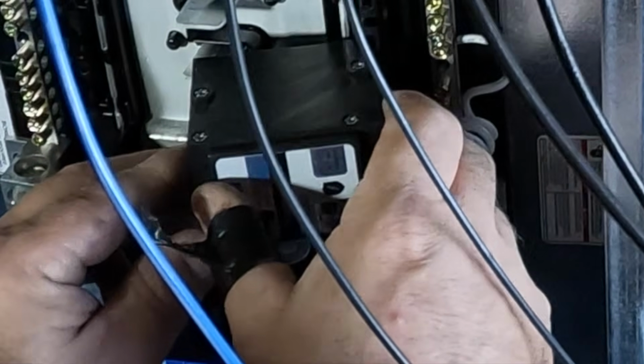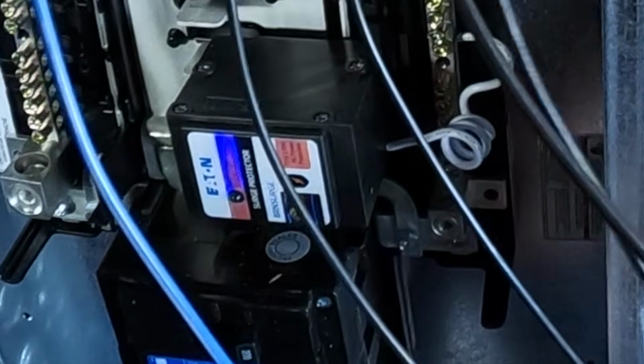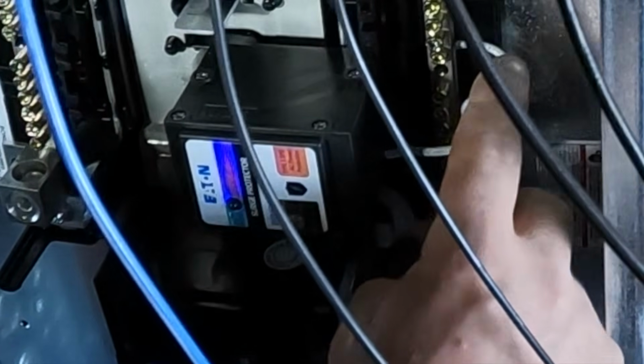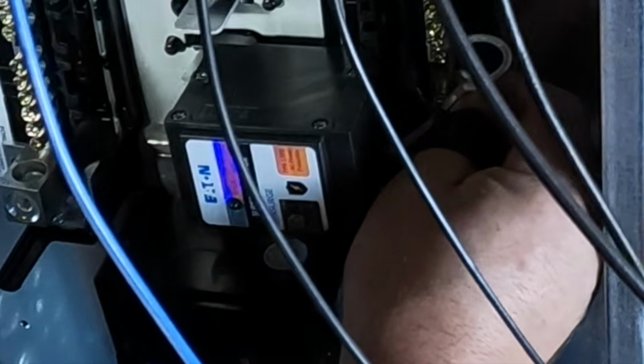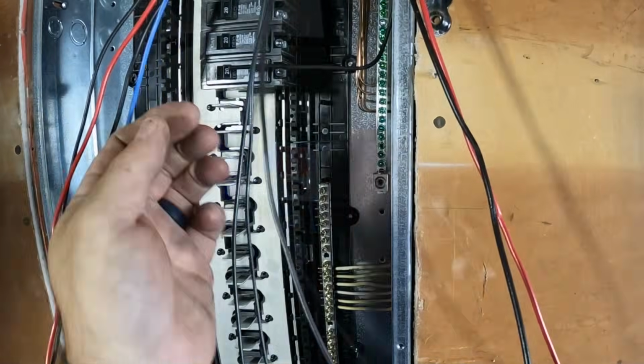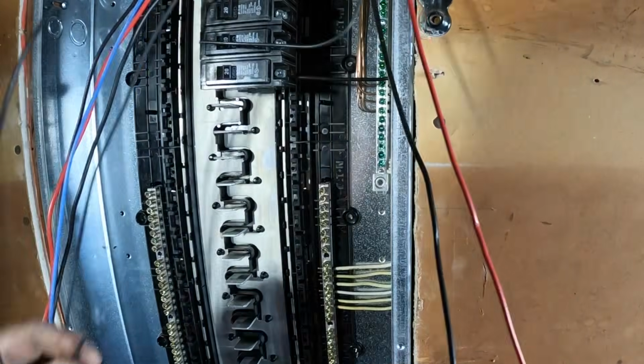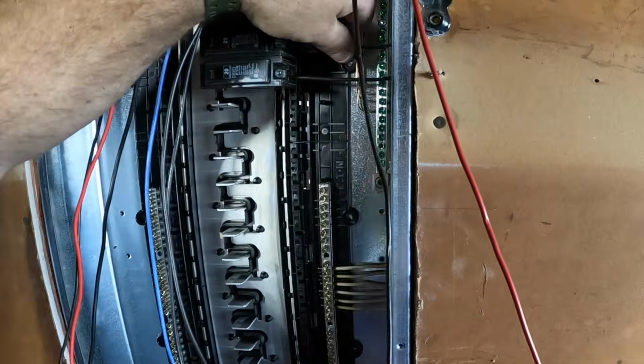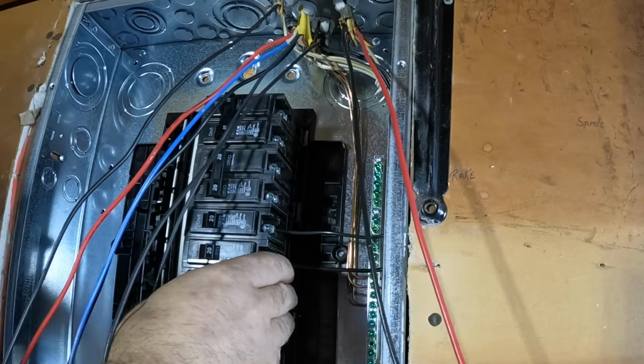Here is the required surge protector. Now, this is a plug-on neutral panel, but they gave me a surge protection device with the pigtail neutral that connects right to the neutral bar. Then from there, we'll start installing the circuit breakers. I like to do these one at a time and try to install them as neat as possible.